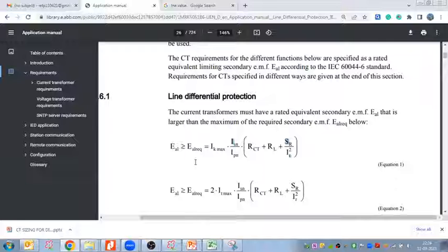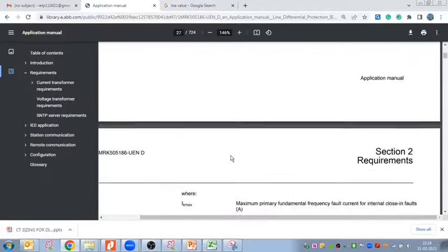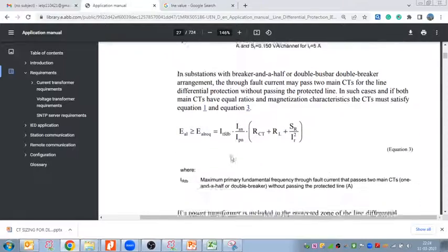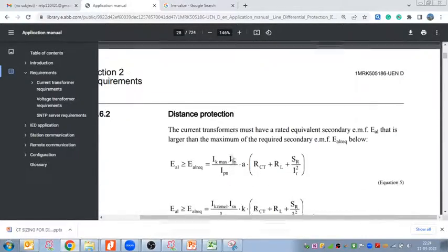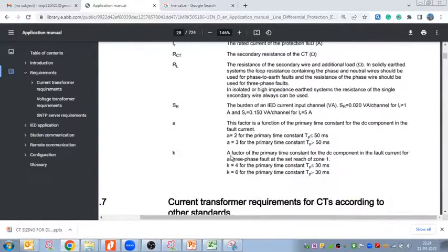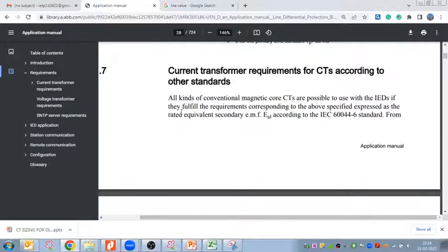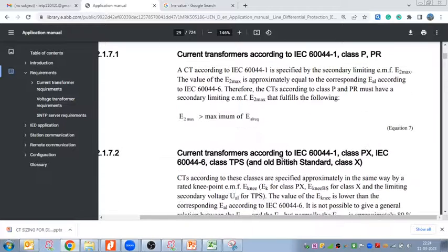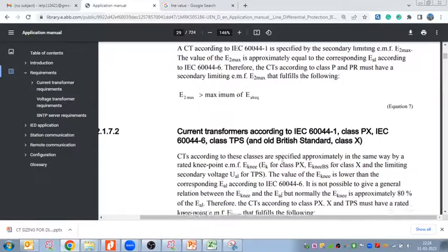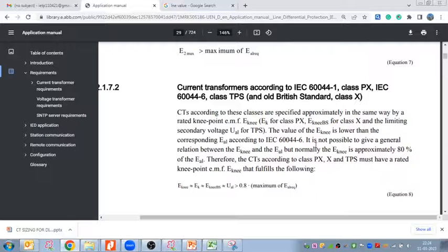If you see this, there is one more point. This is telling, let me check, current transformer requirement for CT according to other standards. Other standards they are telling here: current transformer according to IEC class PX, IEC 60044 class TPS, and old British standard class X. So British standard tells us only class X.